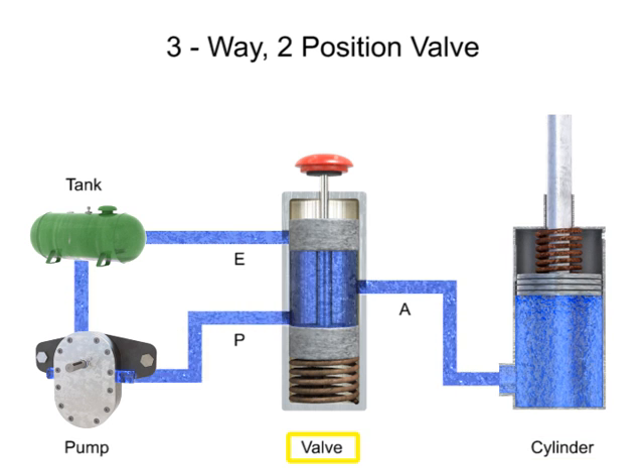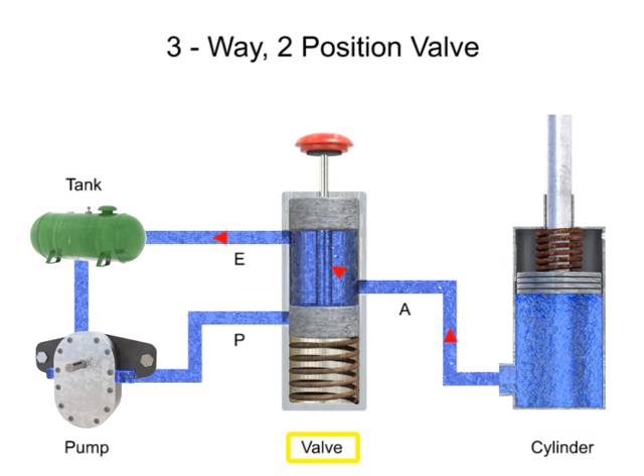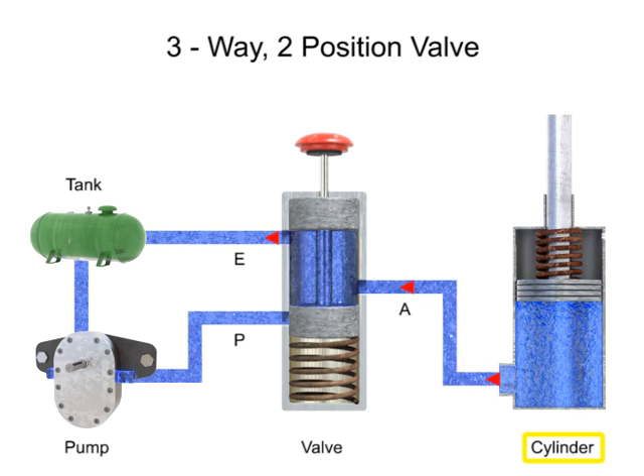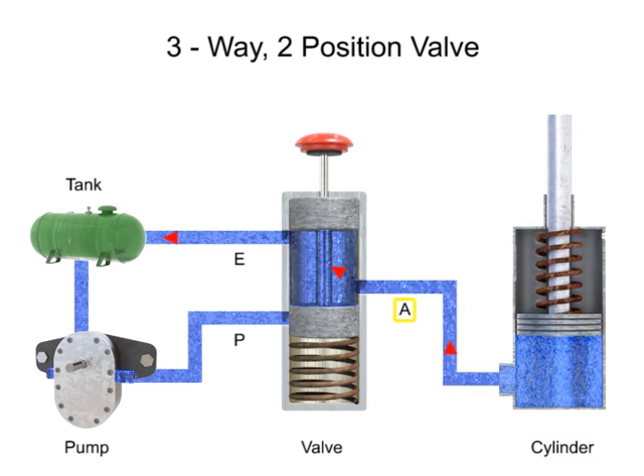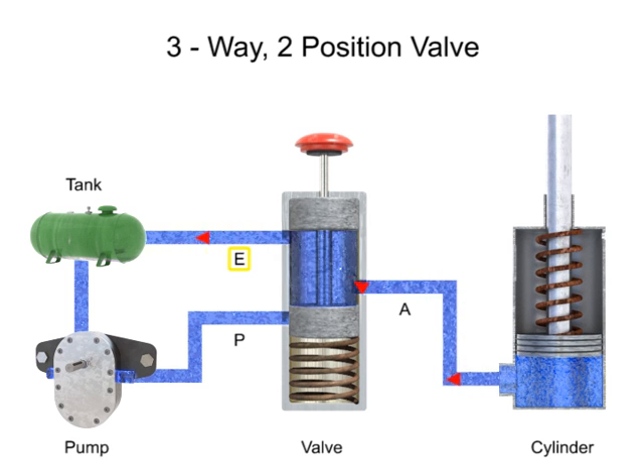When the valve de-energizes, the spool returns to position 1, pressure port P is blocked and exhaust port E is opened. The cylinder retracts and fluid flows from the cylinder through port A and out exhaust port E. From there, the fluid returns to the tank.